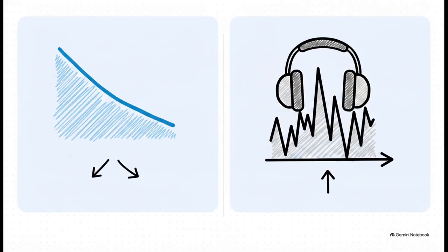Now, the absolutely crucial part here is how the software tells the difference between a real power drain and a fake glitch. It uses what's called an equivalent circuit model, or ECM. The BMS algorithm compares real-time voltage against this model. A real electrochemical discharge, well, that has a relatively smooth slope that matches the ECM. But a loose wire, a microcrack, or an EMI attack creates a sharp, violent spike with an extreme dV/dt rate. It's kind of like using noise-canceling headphones. The algorithm specifically identifies and filters out that static to zero in on the real threat.